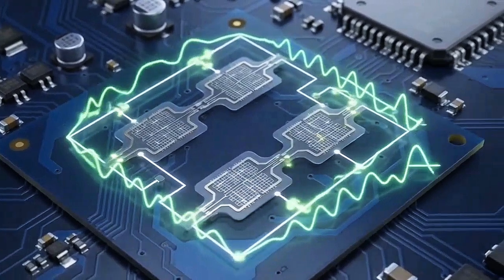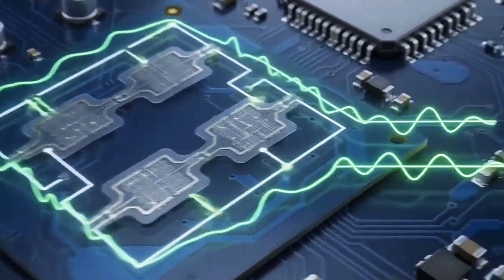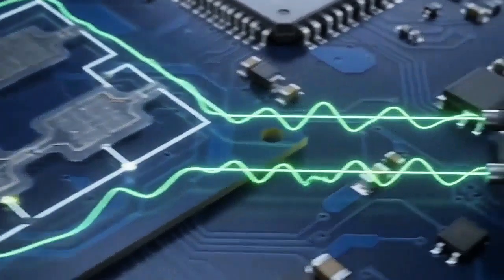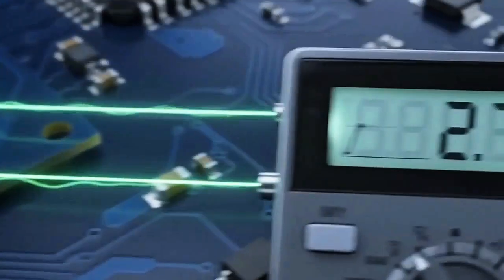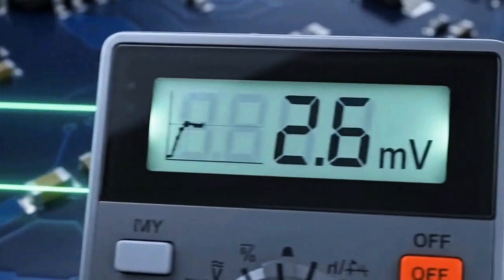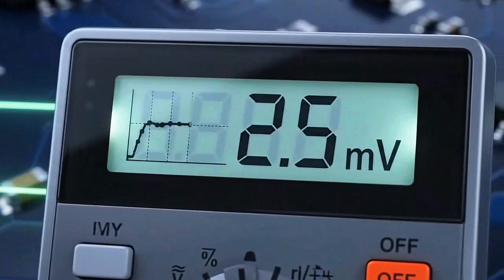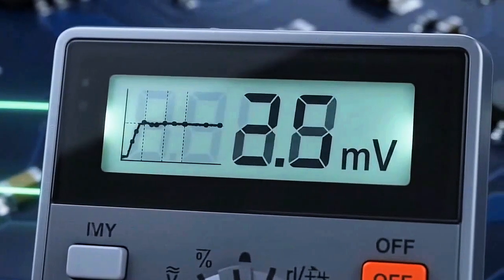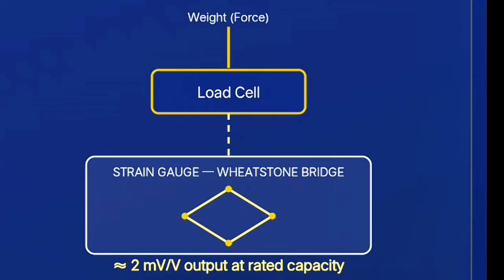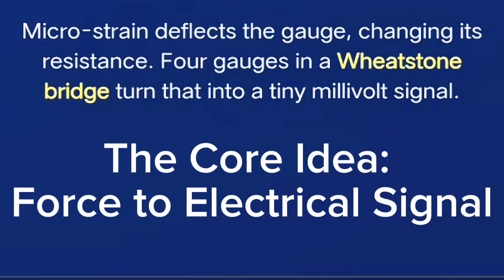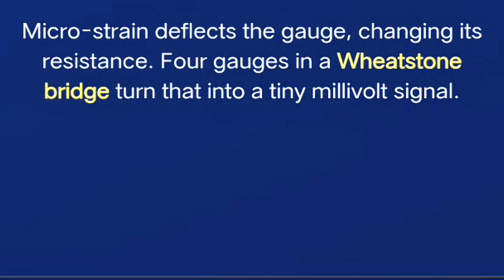changes its electrical resistance. We arrange 4 of these strain gauges into a Wheatstone bridge circuit. 2 arms go into tension, 2 go into compression, and the bridge produces a small millivolt output proportional to the load, typically in the range of 2 millivolts per volt of excitation at rated capacity. That signal is tiny, it's noisy, and it needs to travel from a load cell mounted in a dusty, vibrating plant environment back to a junction box and then to an indicator or a PLC analog input without picking up interference. That journey, and everything that can go wrong along it, is what this series is really about.